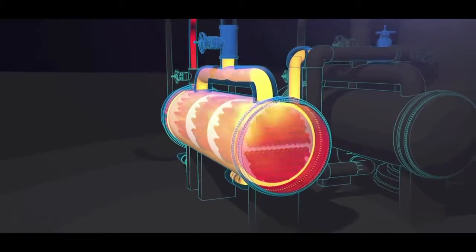When identifying overpressure protection requirements for heat exchangers, engineers should evaluate the scenario that caused the Williams explosion. The hot side of the heat exchanger was operated while the cold side was blocked in. In this scenario, just having a pressure relief valve available could have prevented the explosion.